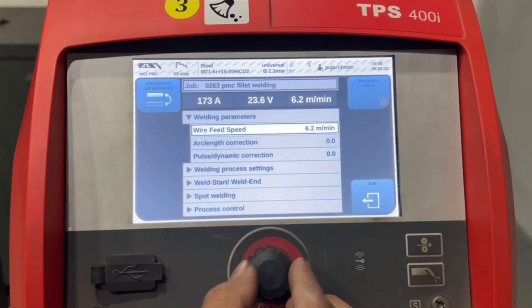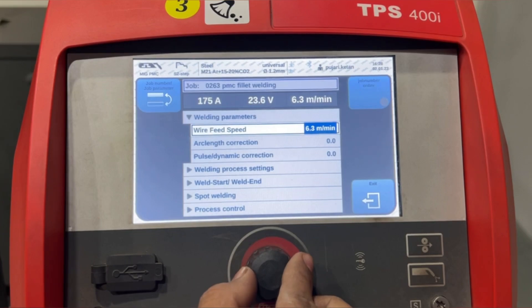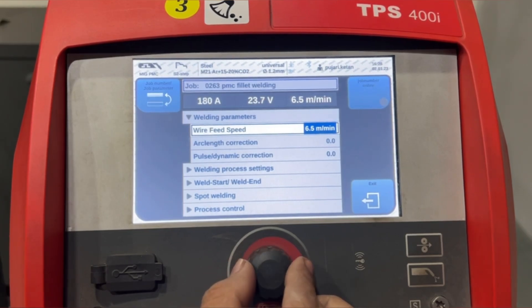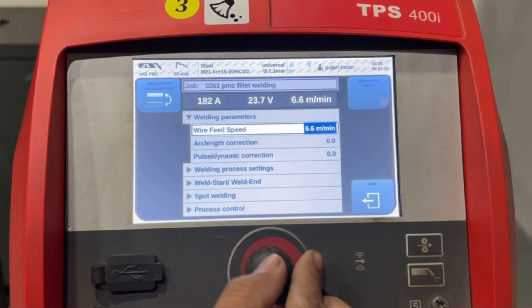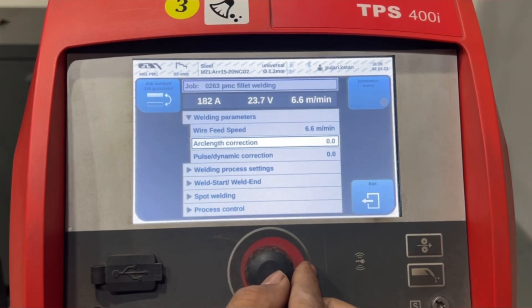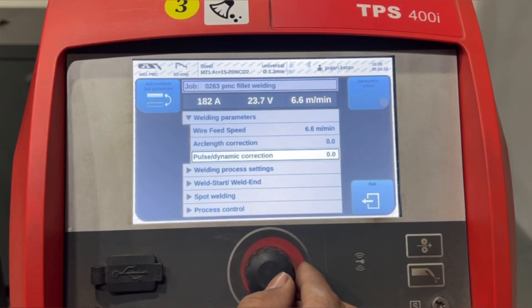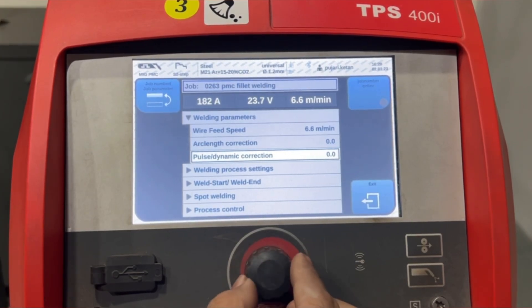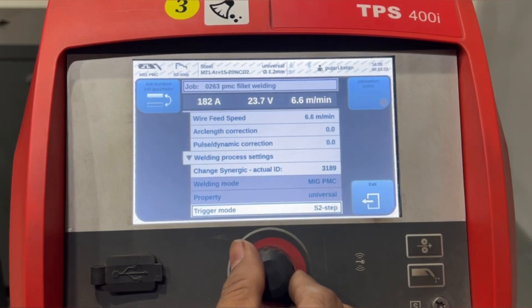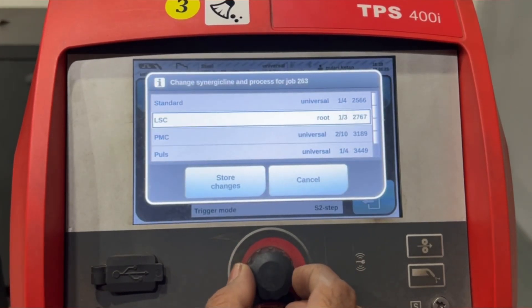You can now optimize the parameters. The main parameter here is wire feed speed — when you change wire feed speed, the current and voltage also get changed. There is also the option for arc length correction and pulse dynamic correction. With the new firmware version, you can also change the synergic line in optimize job.